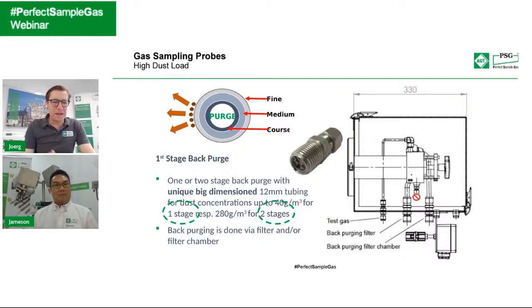Now let's pretend, Jameson, someone made the big mistake and did not buy the probe from us. I mean, we are kidding a little bit here. It's really the case that you could buy a PSG Plus probe, for example, without back purging, and later on we could add this option to the probe. But let's now pretend, Jameson, someone didn't do it. So maybe some strategies, if you say, okay, my probe has the problem that it got clogged quite some time, a pre-filter could be an option. I think this is also something we see. In our technology, in our architecture, in our probe design, we don't need a pre-filter because we have this big filter surface inside the probe body, but a pre-filter is something we could do.